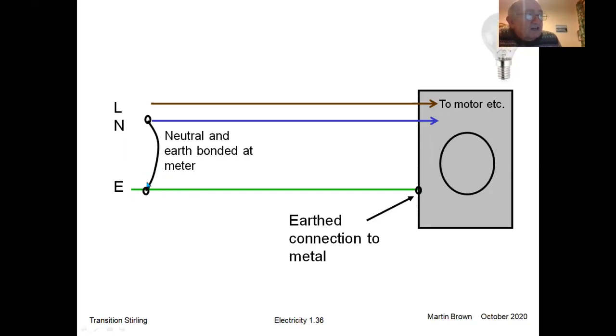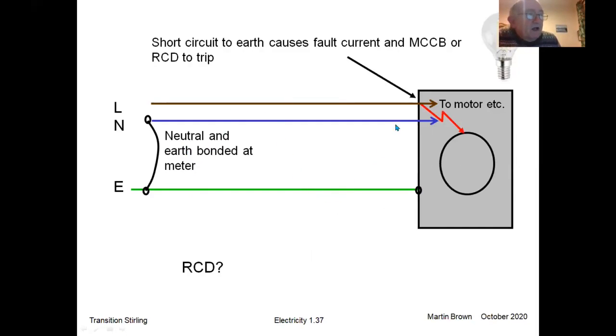Neutral and earth tied together at the meter or at the consumer unit. Now, what happens if there's a short from live to earth? Well, if there's a short from live to earth, it's effectively a short from live to neutral. So it's a short circuit, so hopefully a fuse will blow or something. But it's not current that's flowing through the neutral wire. It's flowing from live round down to earth.